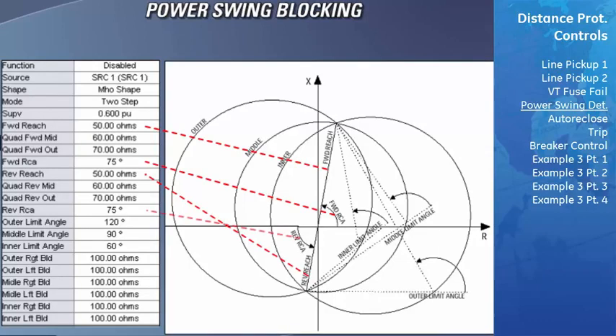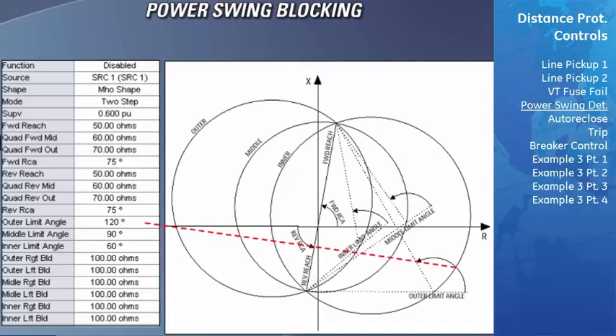The power swing reverse reach characteristic angle specifies the angle of the reverse reach impedance. The angle is measured from the negative x-axis as shown here. The power swing outer limit angle defines the shape of the outer block zone characteristic. If this angle is set to greater than 90 degrees, the result will be a tomato-shaped characteristic. If the angle is set less than 90 degrees, the result will be a lens-shaped characteristic.